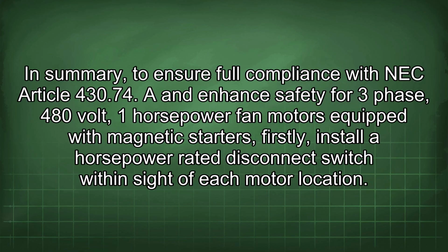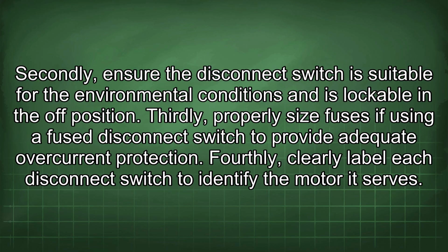In summary, to ensure full compliance with NEC Article 430.74, and enhance safety for 3-phase, 480 volt, 1 horsepower fan motors equipped with magnetic starters. Firstly, install a horsepower rated disconnect switch within sight of each motor location. Secondly, ensure the disconnect switch is suitable for the environmental conditions and is lockable in the off position. Thirdly, properly size fuses if using a fused disconnect switch to provide adequate overcurrent protection.